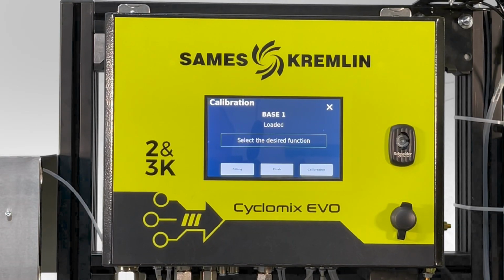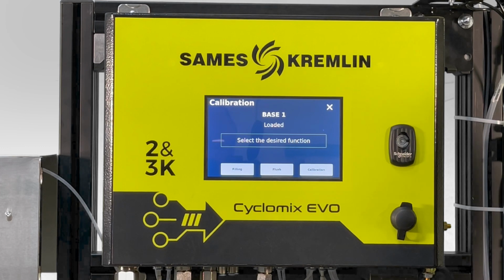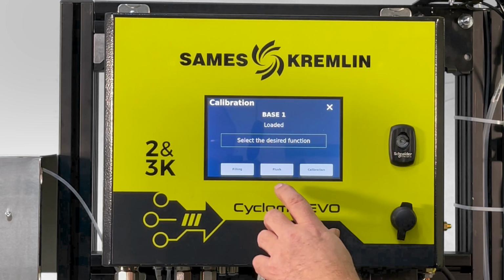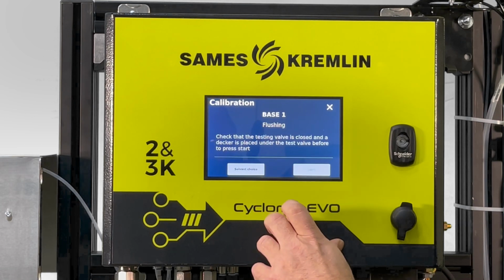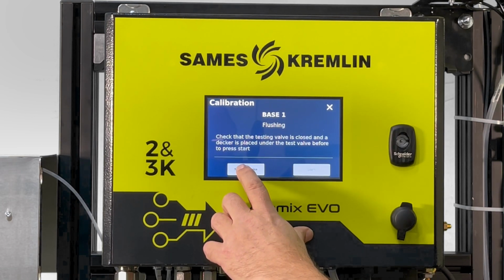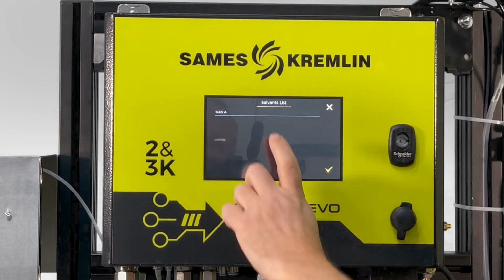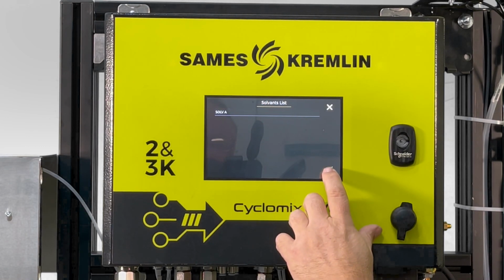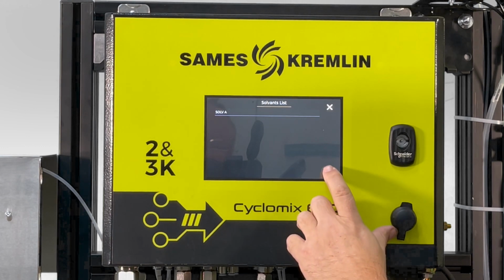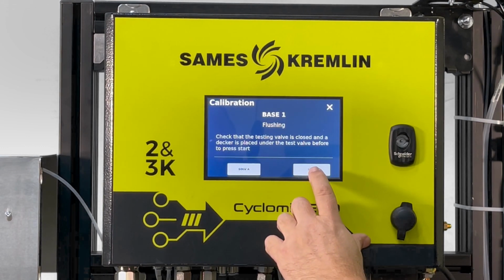So after a calibration, the line is all full of material now. So you have to flush it. So to flush, you go to the screen, you select flush. I have to choose what solvent I want, and there's only one in this list. So I select that, and then I click on the arrow, and I hit start.